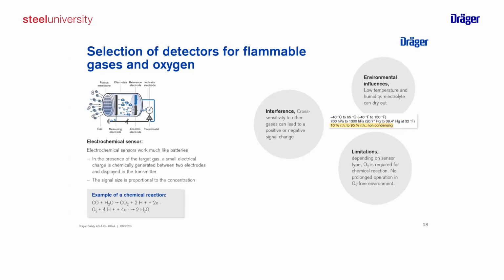Let's have a look at two principles for gas detection. One is electrochemical sensors. Here's a schematic on this. So what we have is the molecules vaporize through a membrane into the sensor. You can compare this to a battery. You have electrodes, you have an electrolyte. On the one electrode, you will have a chemical reaction. You will generate electrons. And if you have a circuit around, then you can measure this amount of electrons and you get an indication.